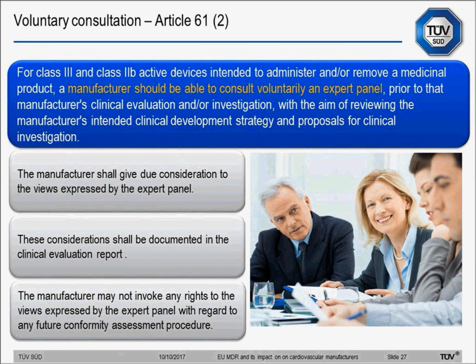There is a mandatory consultation process, and this is required for Class 3 implantable devices and Class 2B devices intended to administer or remove a medicinal substance. For those devices, the notified body is required to review the clinical evaluation report and the post-market clinical follow-up plan, to prepare a report, shown in this slide with the acronym CEAR, the Clinical Evaluation Assessment Report.